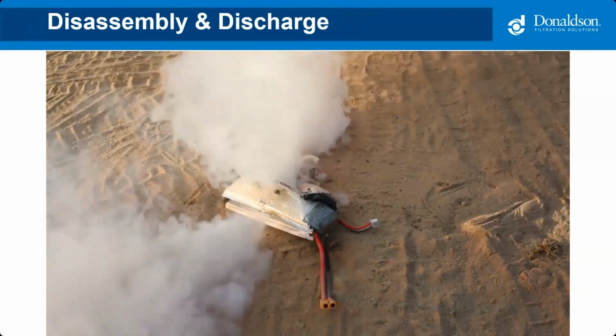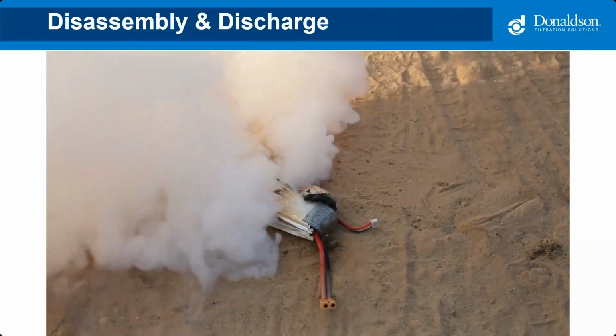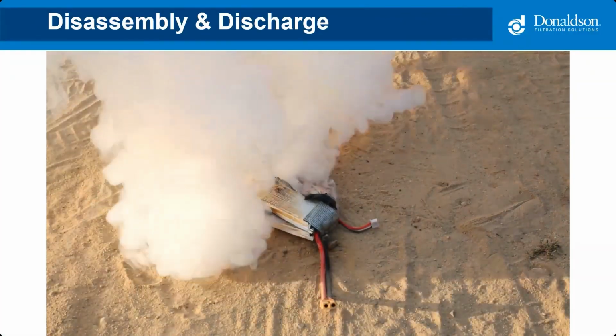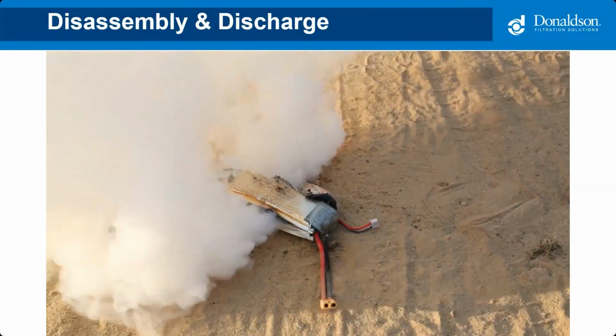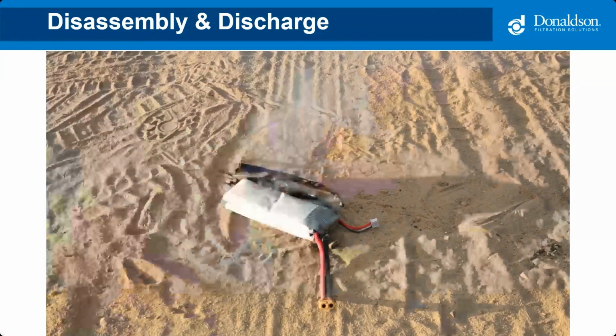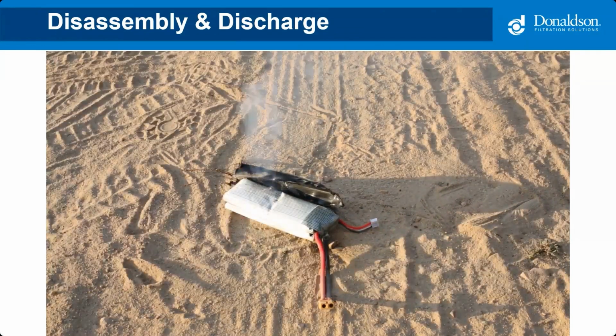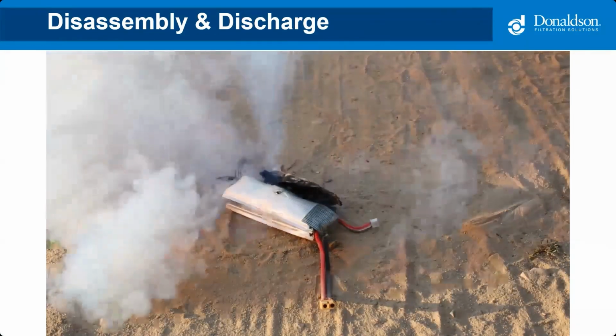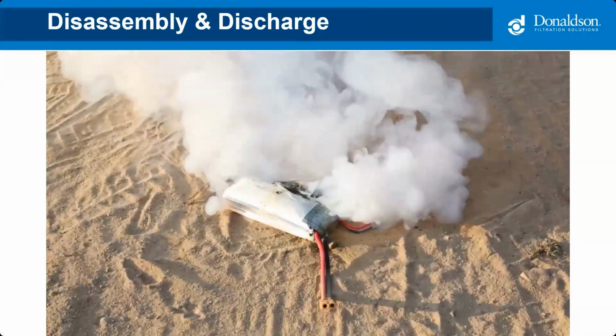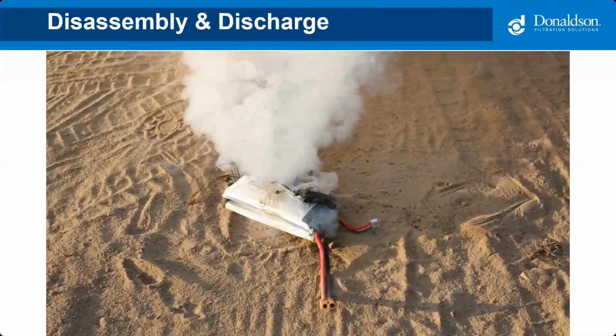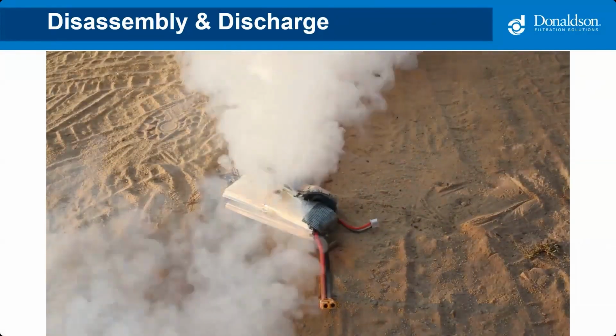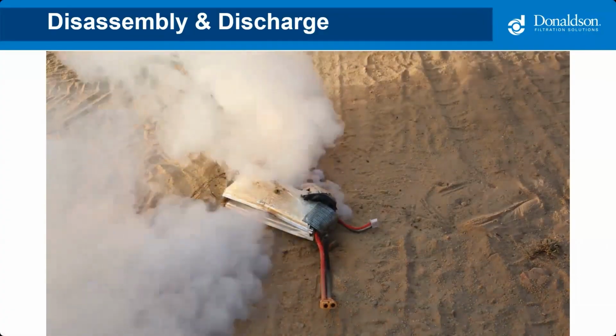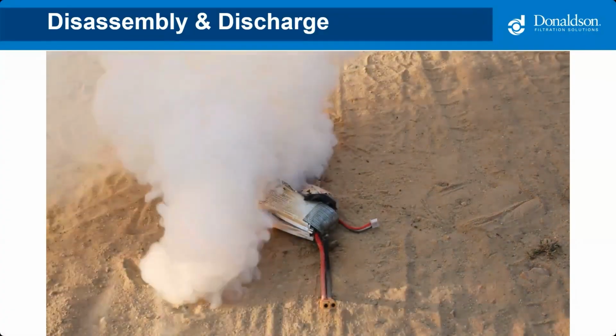But another common method is to use a highly concentrated saltwater submersion to discharge. This is when we have a variety of smaller batteries, perhaps. This method makes an immense amount of combustible hydrogen gas. And per industry experts, hydrogen needs to be diluted to below 4% with inert gas or airflow to operate safely.